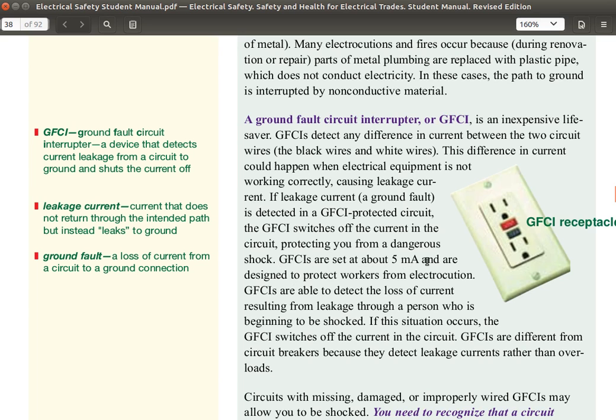GFCIs are set to about 5 milliamperes and are designed to protect workers from electrocution. That means if you have 100 milliamperes coming out of the plug and 95 or less milliamperes coming back, then the GFCI will detect that difference. If 96 milliamperes are coming back, only 4 milliamperes are missing, so the GFCI would not detect that. However, the person probably would be able to let go of the drill.